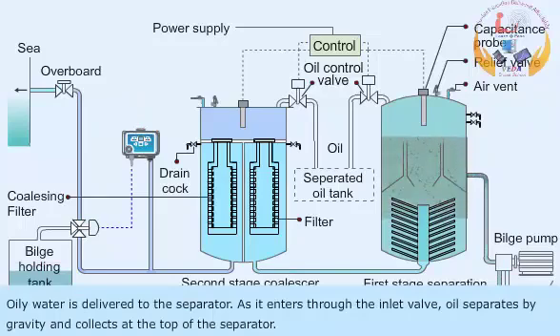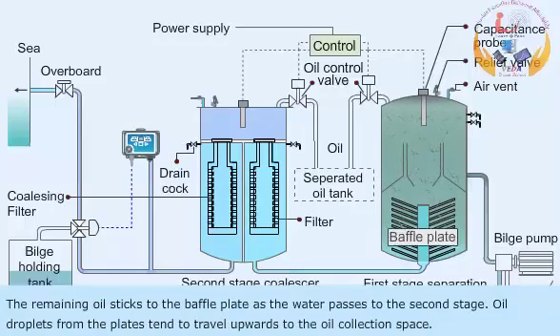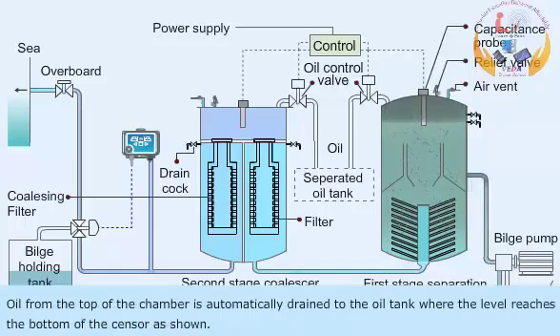Oily water is delivered to the separator. As it enters through the inlet valve, oil separates by gravity and collects at the top of the separator. The remaining oil sticks to the baffle plates as the water passes to the second stage. Oil droplets from the plates tend to travel upwards to the oil collection space. Oil from the top of the chamber is automatically drained to the oil tank when the level reaches the bottom of the sensor.